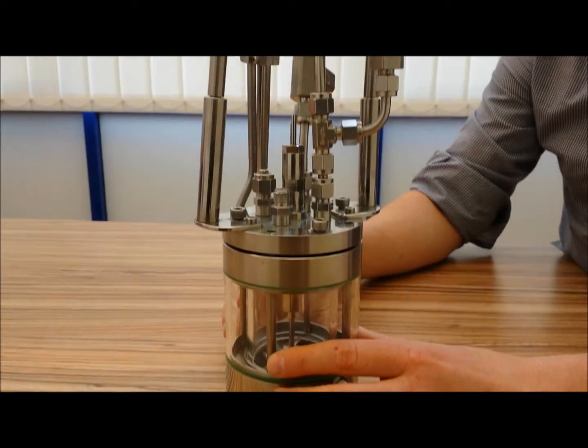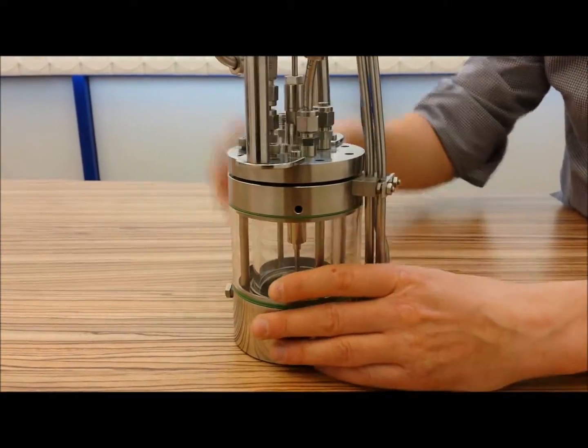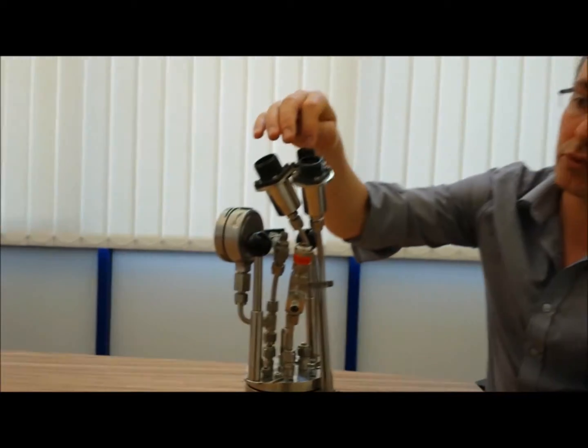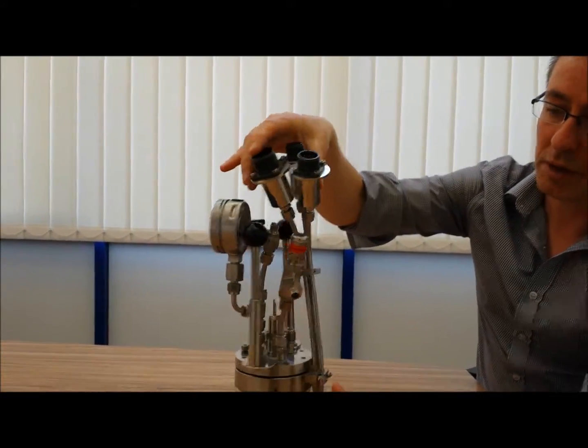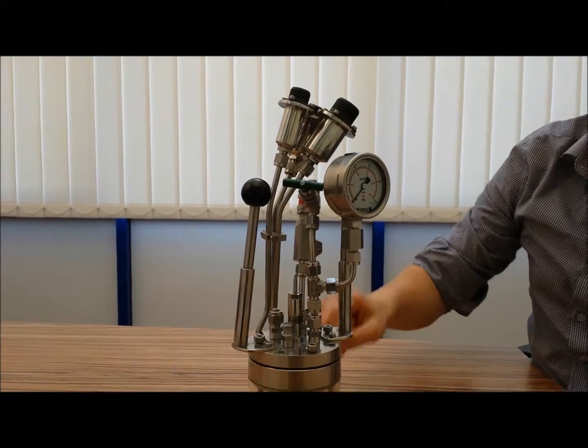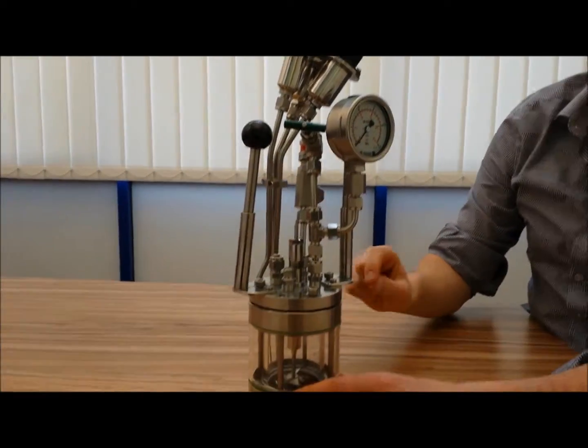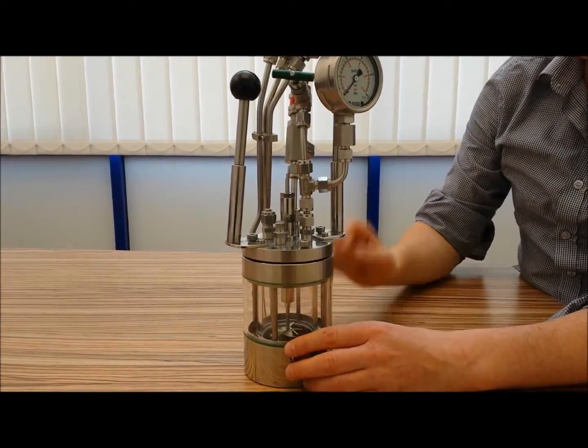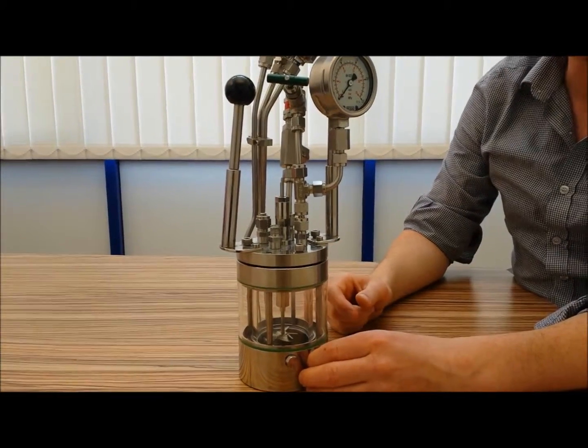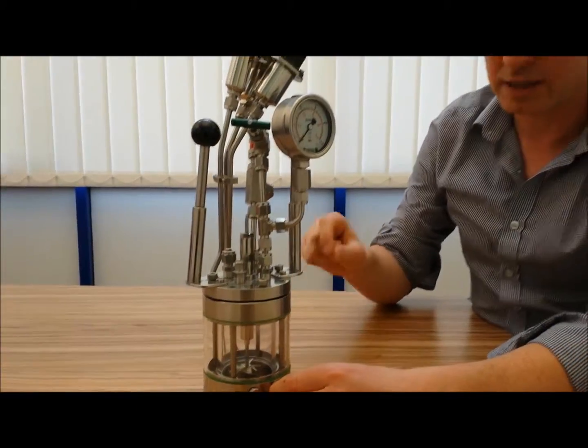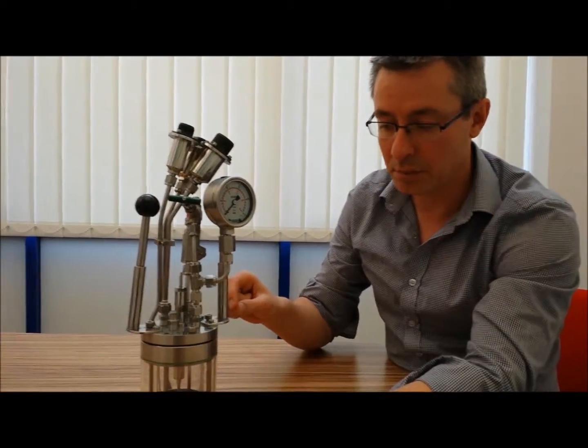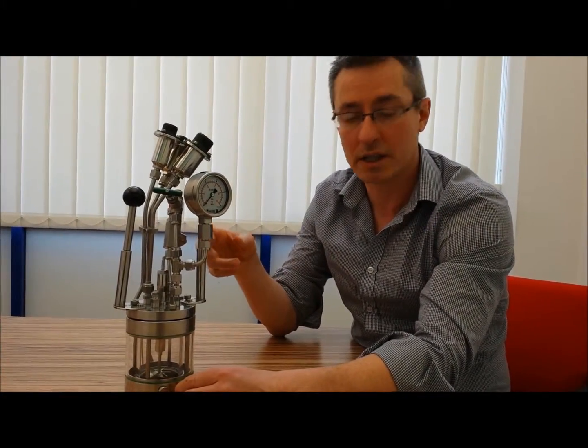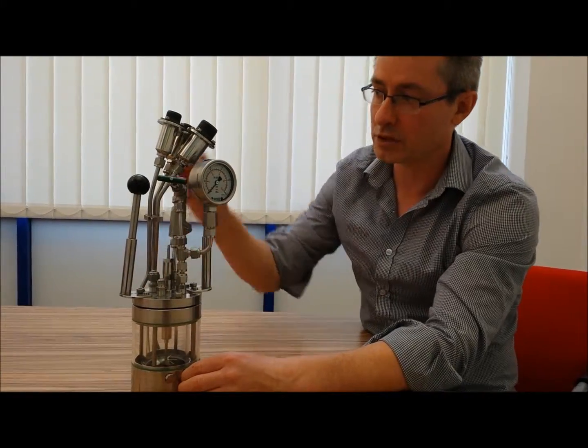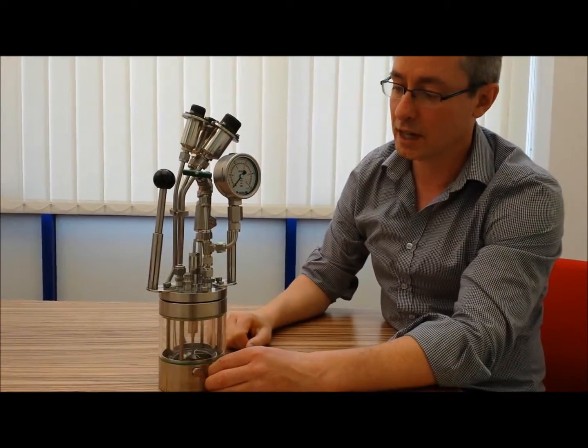So what I'll do is explain what the 1, 2, 3 connectors here are. In a bit we're going to have a look inside the reactor, and we're going to first of all see that there's a temperature probe in there, and we're also going to see that this one is fitted with a validation heater. You absolutely do not need to calibrate this calorimeter ever, but some people like to have a calibration heater because once a year they like to put in a known power and see that the calorimeter responds in an appropriate fashion. So I mentioned that because there are 1, 2, 3 connectors on here.